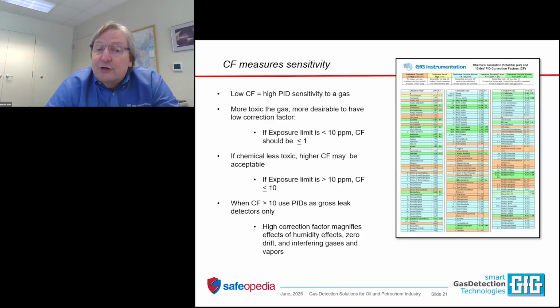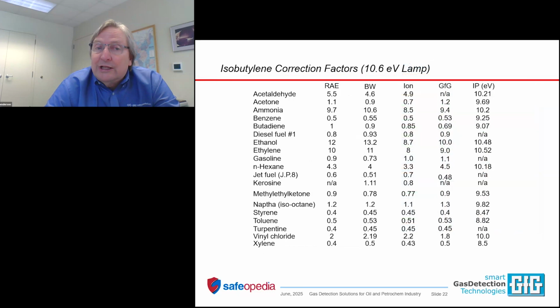If the correction factor is greater than 10, now you're talking about having a sensor that is better used as a gross leak detector. It's not going to give you much in the way of an analytical response. It's a much more qualitative response. And this is why you don't want to use some other manufacturer's table of correction factors interchangeably with a different brand of instruments.